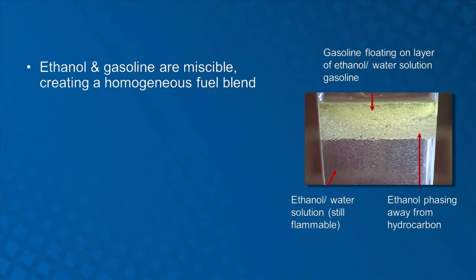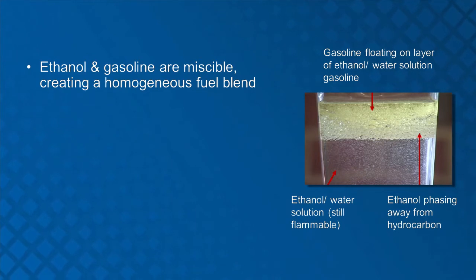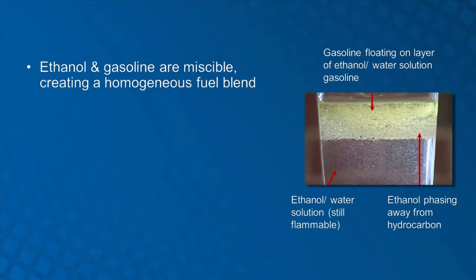Water introduced into ethanol-gasoline fuel blends has a dramatic effect. Without water, ethanol-gasoline blends remain homogeneous or mixed. Since ethanol has an affinity for water, it is not necessary to add gas line antifreeze to an ethanol-gasoline blend, as the ethanol will absorb trace amounts of water. However, when using water to extinguish a fire during emergency response, water can pull the ethanol out of the blend, resulting in a separate layer comprised of water, ethanol, and some hydrocarbon content. The gasoline will remain in the top layer. Although rare, phase separation can also occur in fuel storage systems where water is present.